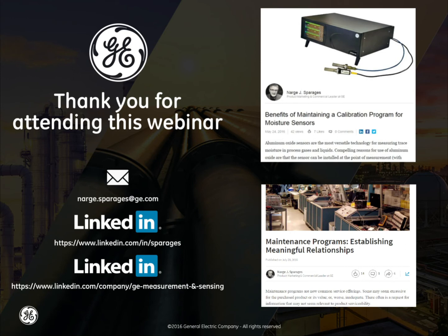So we've had sensors come back for calibrations for over 20 years. Sensors that we shipped back in the 1990s and in fact even 1980s are still in service today, and that's a testament to the calibration program and cycle that the customer has put in place. It's also a testament to the sample system design and operation of the sample system as it keeps the sensor from being exposed to contaminants, erosive or corrosive items. So from a shelf life perspective and a life cycle perspective, I would say that there is no detriment for keeping the sensors.